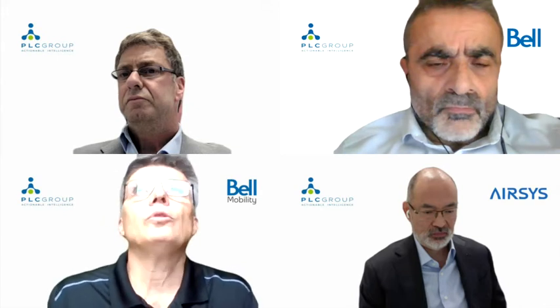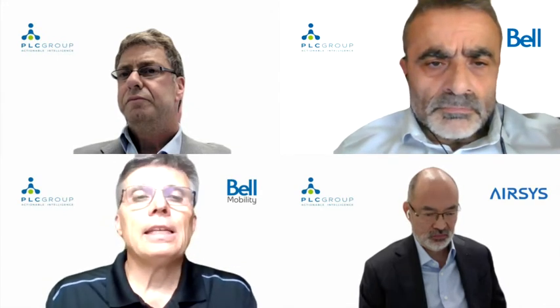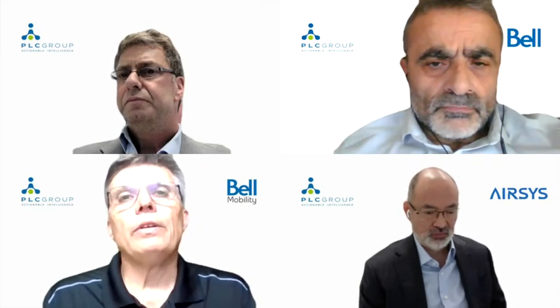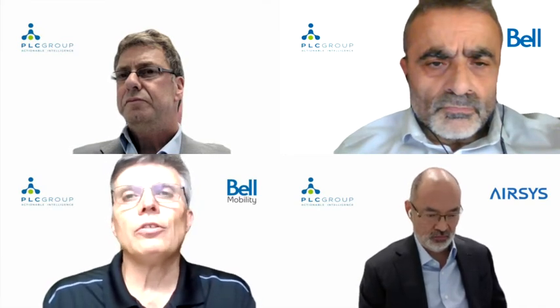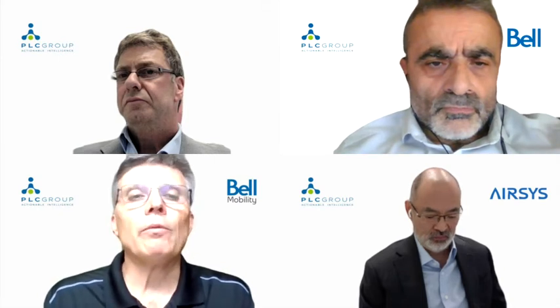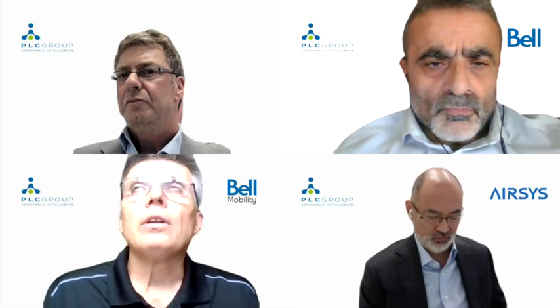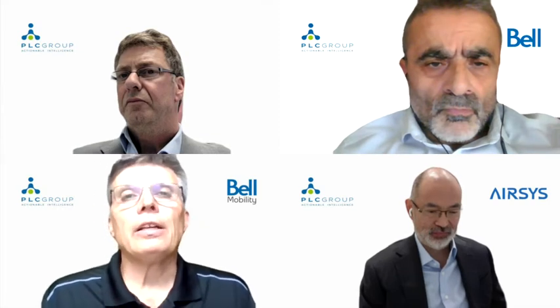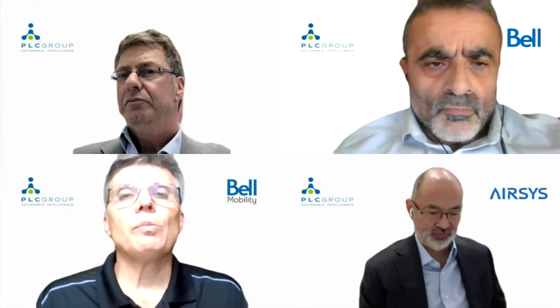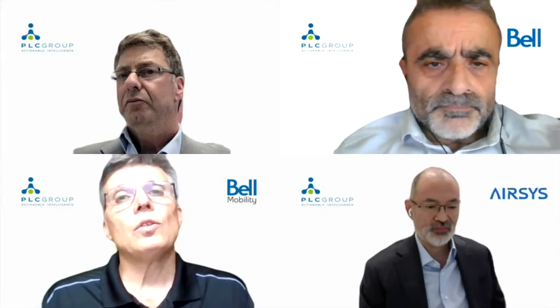There's so many options available to you. We didn't talk about cabinets, and that's a really tricky business. We've developed solutions for cabinets as well. If you lose AC power for an air conditioner in a cabinet, you could overheat in minutes. We've also been running out of air conditioner capacity—6,000 BTU won't cut it anymore, and 10,000 probably won't either, we're there. DC air conditioners are another challenge since we're already struggling to power 5G and its BBUs, which are very hungry. The lowest power consumption comes from free cooling. Now you'll also have lithium batteries, which don't charge below freezing, so that's another issue. It's a complex world.